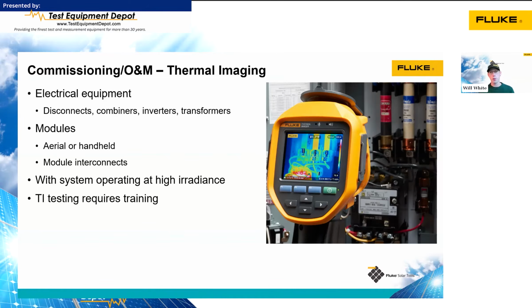You can't just pick up a thermal camera and go out in the field and expect to get high quality data. You really need to get the training that goes along with it to be able to take good photos and get good information. In this photo here, we've got a picture of a fuse disconnect. You can see that the fuse on the left-hand side looks a little cooler than the fuse in the middle and the right. That could just be that it's a different fuse, or it could be there's less current flowing through that circuit than there is through the other two, but it warrants a little bit further investigation there.